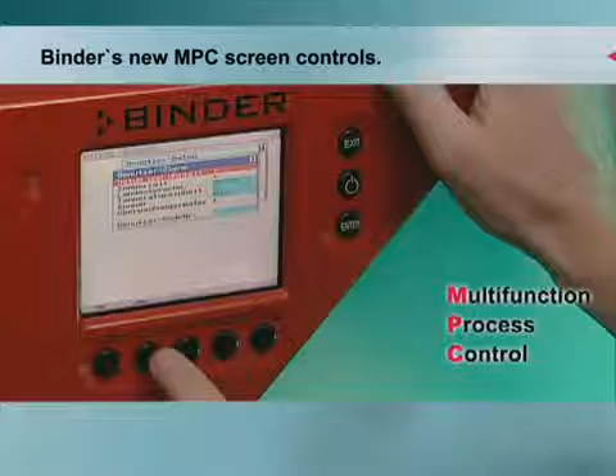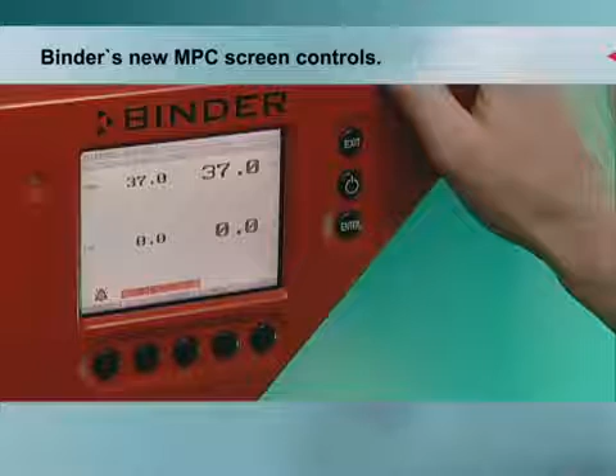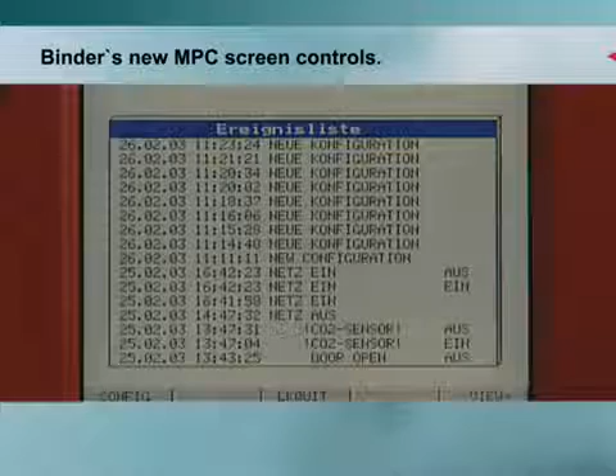Important data such as CO2 content and temperature are precisely and continually recorded and can be accessed at any time. The whole culture process is documented by this system, a fundamental precondition for conforming to GLP/GMP working conditions. All functional system interventions and changes are continually monitored by the device as an events list, guaranteeing a maximum of process monitoring.